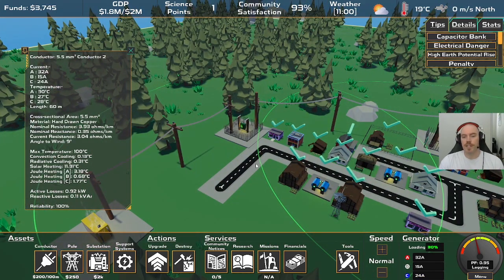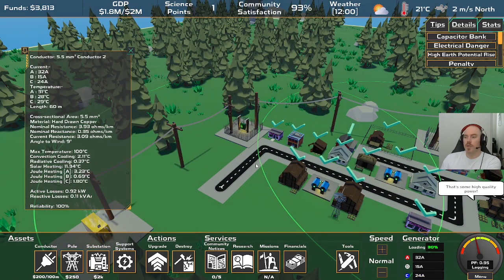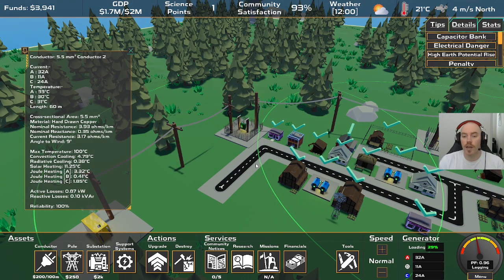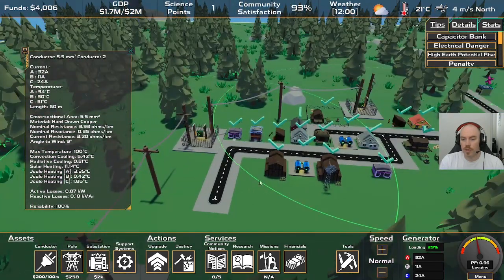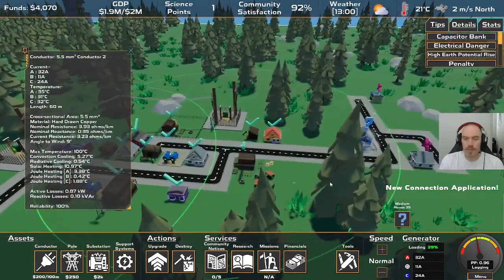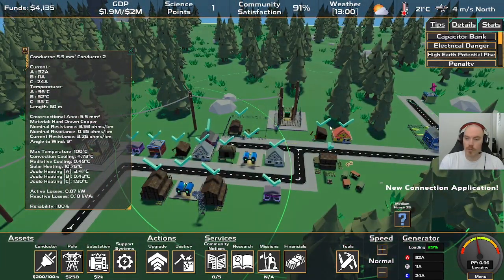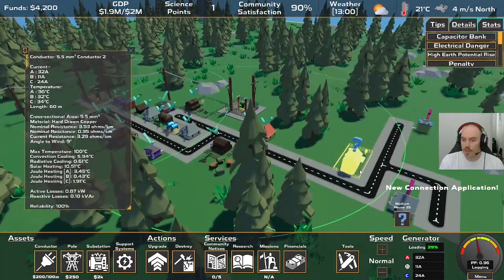That's essentially the industry standard for any modeling software for a power utility. So if any utility comes along and is going to model a new suburb, put in some conductors, and determine what kind to use based on how they're installed and what loads they'll have in the substations, they'll be using IEEE 738 most certainly.